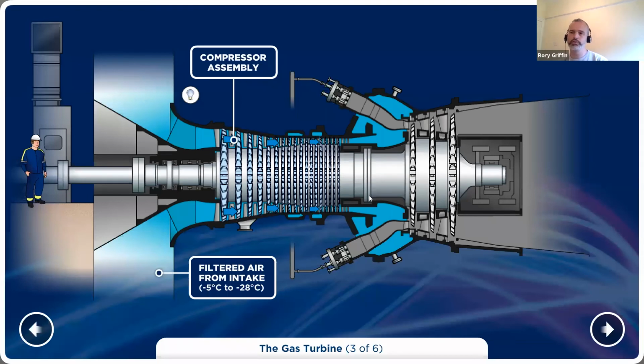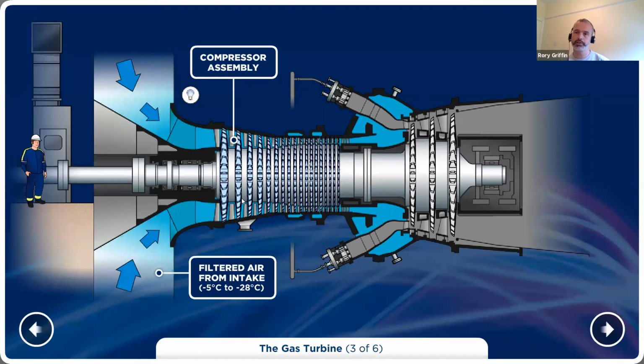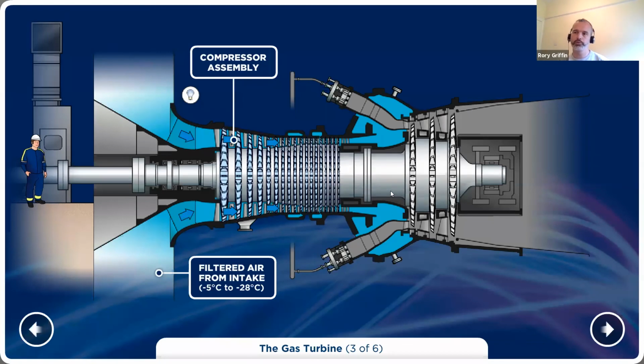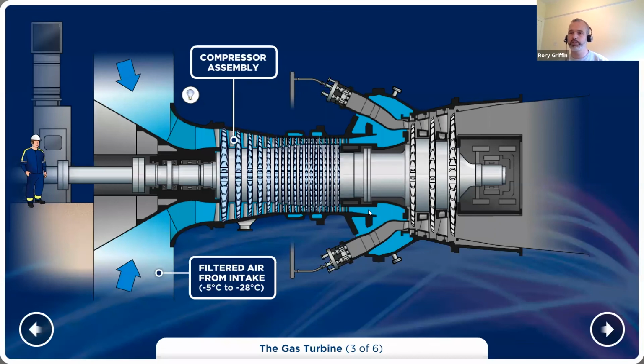But generally, like during an under frequency event, the machine will slow down. So what the machine initially will try to do is make up for the loss of air by increasing the gas fuel in. But there's limitations in that because you don't want your fuel mixture too rich. And also by adding more gas, you're going to increase the pressure here, and the compressor might not allow that. It'll say, look, the pressure on the discharge end is getting a bit high. So the bleed is going to have to open again.